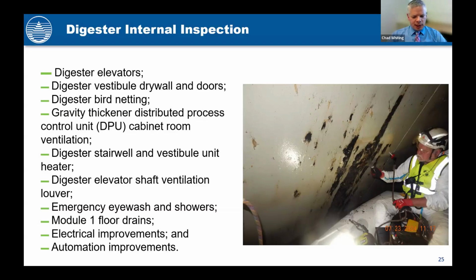We have 2 pumps for each egg, and we often run both pumps in the wintertime to keep that digester mixed and heated, because our flow rates range from 800 to 1,000 gallons per minute. So we want to go with larger pumps to get to 1,000, 1,200 gallons per minute with 1 pump. So then we still have that redundant pump in reserve if something were to happen to one of those recirculation pumps.